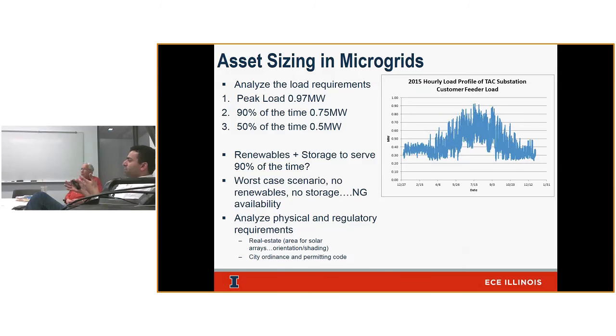But you can also consider the different times of year. If 90% of the time you're at 0.75 megawatts, maybe some assets can operate available 90% of the time, with more of a backup topology for other assets providing that 1 megawatt support. When we started designing, we looked at renewables plus storage and asked could that combination provide the load 90% of the time? Then for the worst case scenario, when you don't have renewables or storage, what asset provides that core reliability to the microgrid - in our case, natural gas.